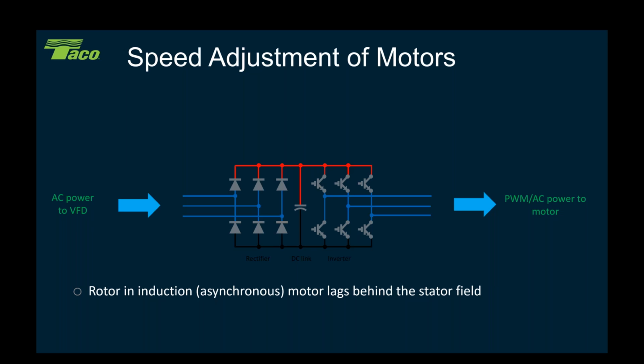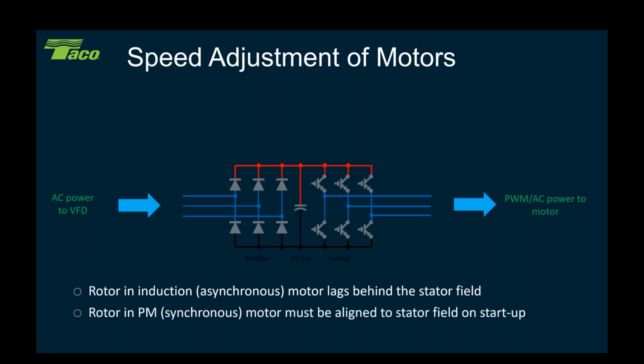And by doing that, in an asynchronous motor, the rotor lags behind the stator field, and that's what's creating that rotation, okay? And again, like I was saying, when we start up a synchronous motor, we have to get those 2 magnetic fields in alignment before we allow it to start. That's why it's imperative that you have a VFD attached to that synchronous motor or permanent magnet motor, because of that need to get those 2 fields lined up.